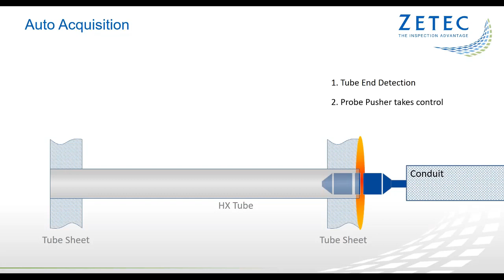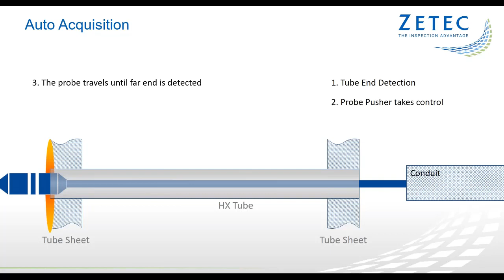Once the operator inserts the probe into the tube end, the system will sense the signal from the probe, and at this point the probe pusher will be engaged. The probe will travel until it reaches and detects the far tube end.